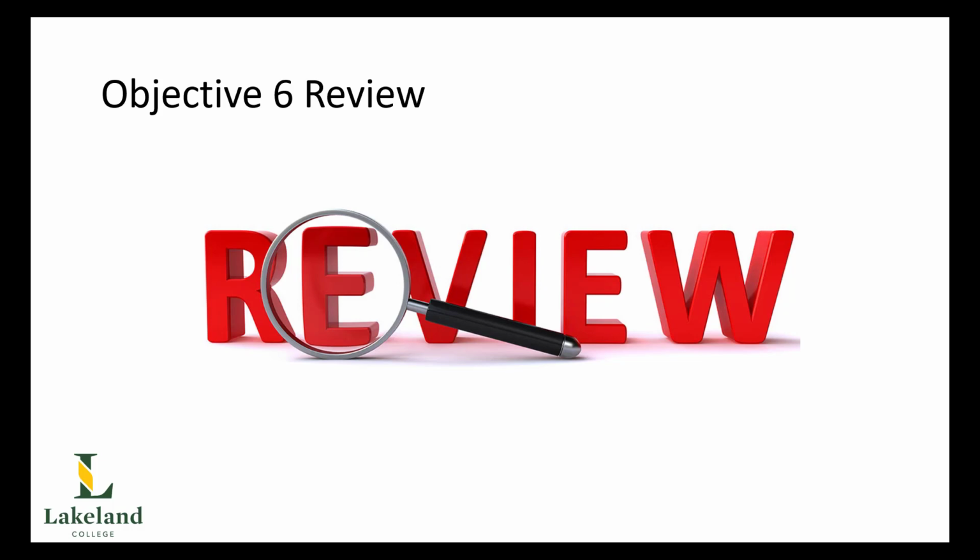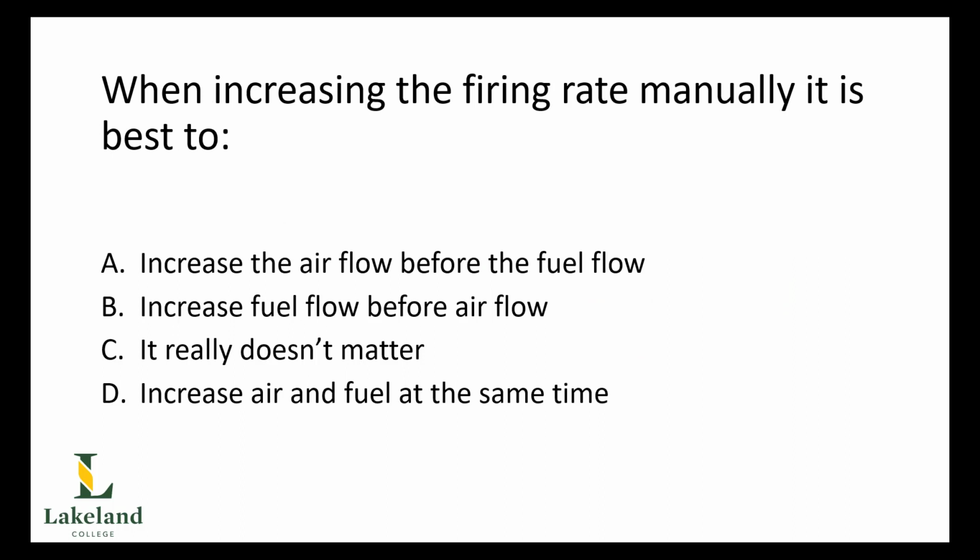So let's check out some typical review questions for this objective. First, when increasing the firing rate manually, it's best to do what? Increase the airflow before the fuel flow, increase the fuel flow before the airflow, it really doesn't matter, or increase the air and the fuel at the same time. Very similar question to the one that we've seen previously. The answer has to be to increase the airflow before the fuel flow.